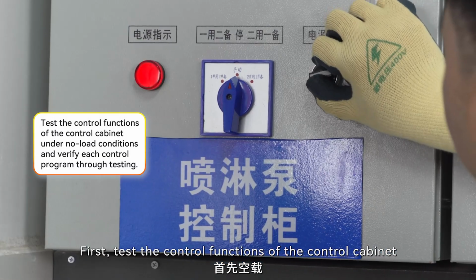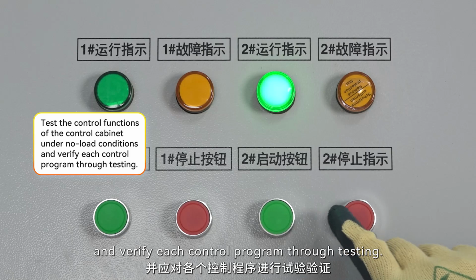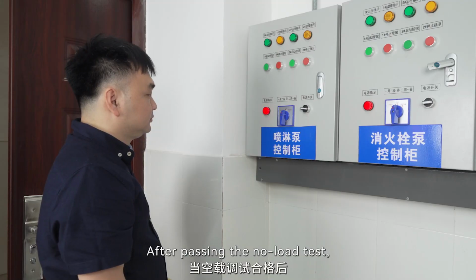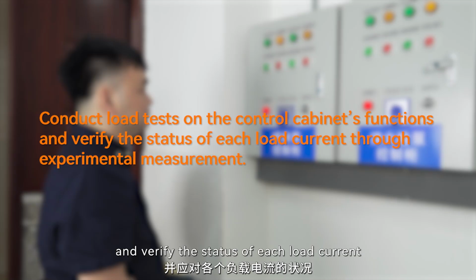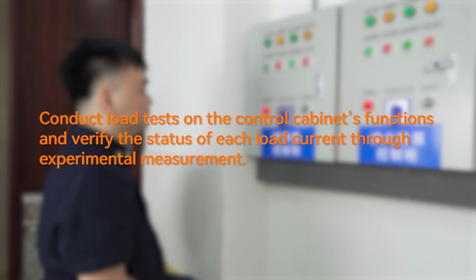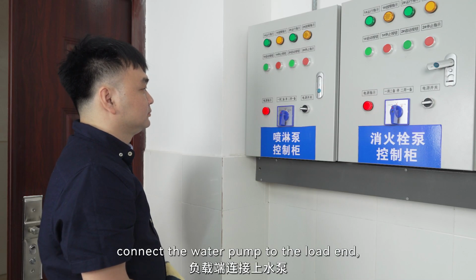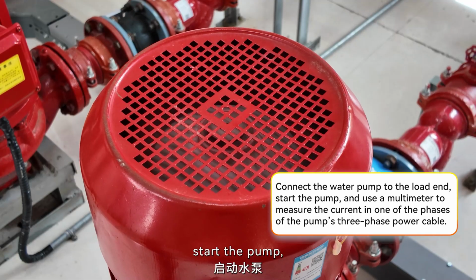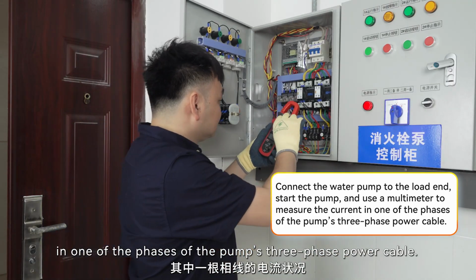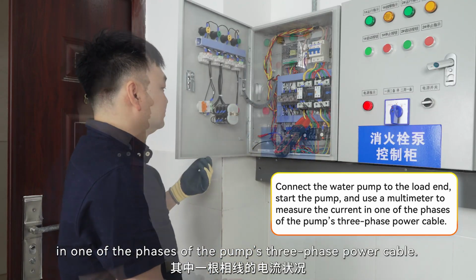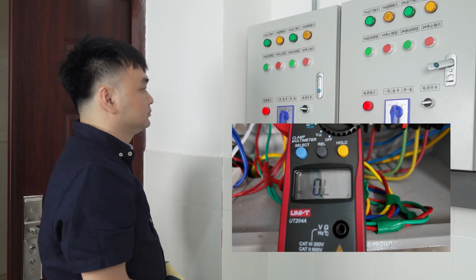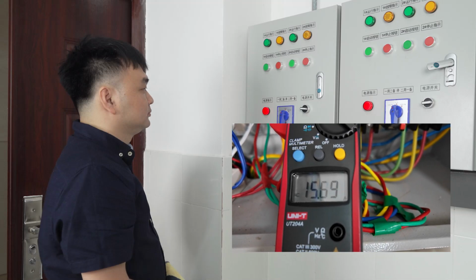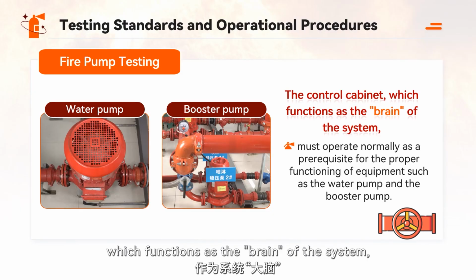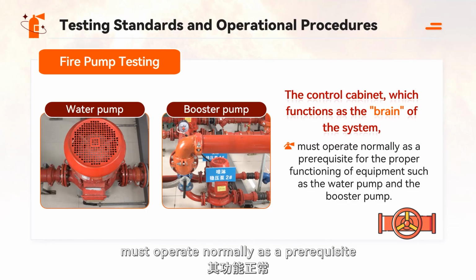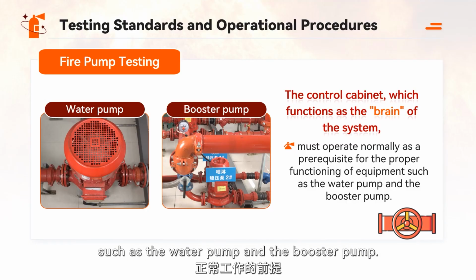First, test the control functions of the control cabinet under no-load conditions and verify each control program through testing. After passing the no-load test, conduct load tests on the control cabinet's functions and verify the status of each load current through experimental measurement. The testing method is as follows. Connect the water pump to the load end, start the pump, and use a multimeter to measure the current in one of the phases of the pump's three-phase power cable. The control cabinet, which functions as the brain of the system, must operate normally as a prerequisite for the proper functioning of equipment such as the water pump and the booster pump.